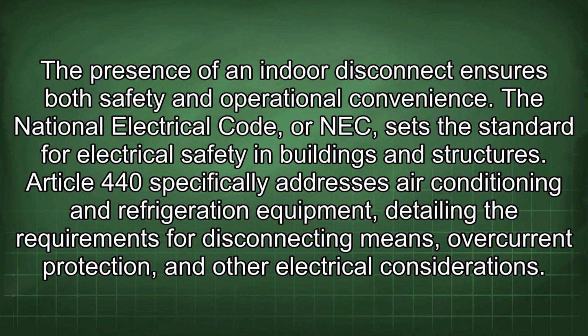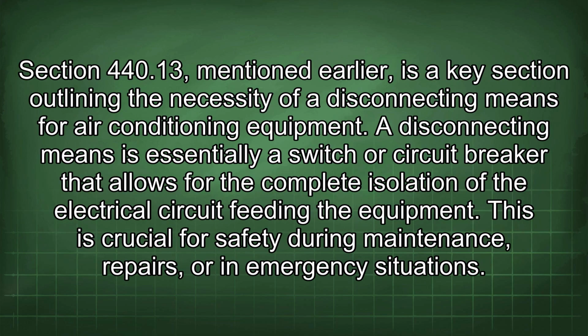The National Electrical Code, or NEC, sets the standard for electrical safety in buildings and structures. Article 440 specifically addresses air conditioning and refrigeration equipment, detailing the requirements for disconnecting means, overcurrent protection, and other electrical considerations. Section 440.13, mentioned earlier, is a key section outlining the necessity of a disconnecting means for air conditioning equipment. A disconnecting means is essentially a switch or circuit breaker that allows for the complete isolation of the electrical circuit feeding the equipment. This is crucial for safety during maintenance, repairs, or in emergency situations.